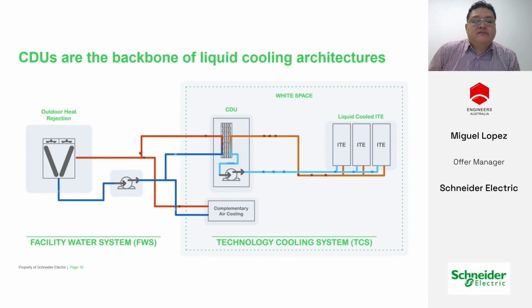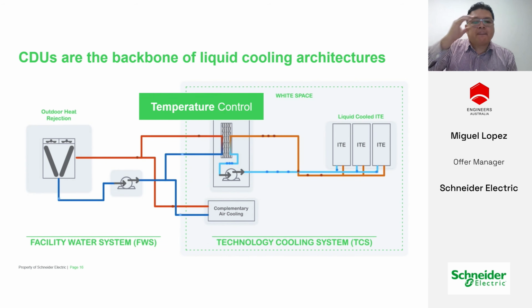So this is something for the novices in the liquid cooling arena. This is a very good graphic showing how the outdoor system interacts with the CDU and how the CDU interacts with your AI-ready equipment. The little box down the bottom labeled complementary air cooling is just showing the possibility of sending some of that cool water from the outdoor heat rejection system to some water-cooled CRAHs or water-cooled InRows for that matter. Moving along to the next slide.